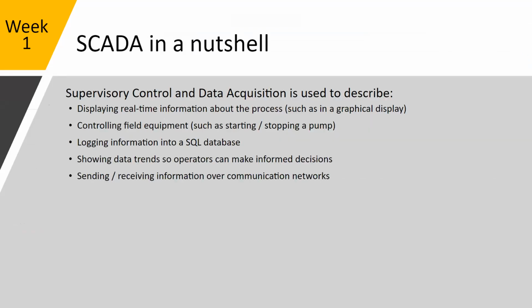So again, the SCADA systems, supervisory control and data acquisition, is used to describe displaying real-time information about the process, such as graphical interface displays, controlling field equipment. This will be interacting with the system for setting set points, starting and stopping, acknowledging alarms, alarm logging, data logging, trending. This would be done through the SCADA system, logging information into databases. SQL databases are all over the place.